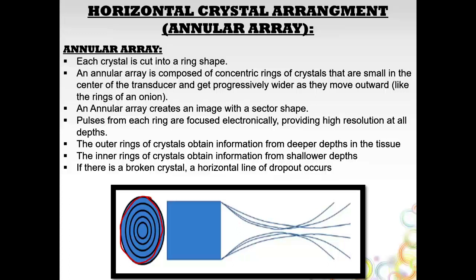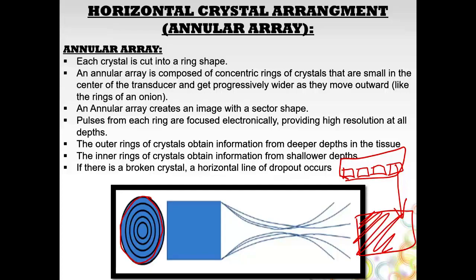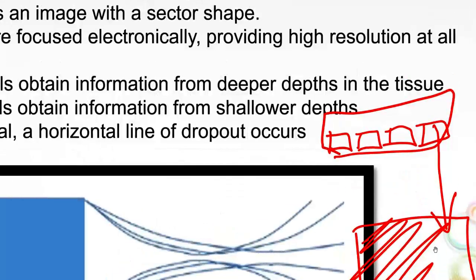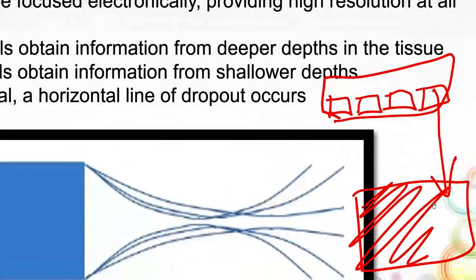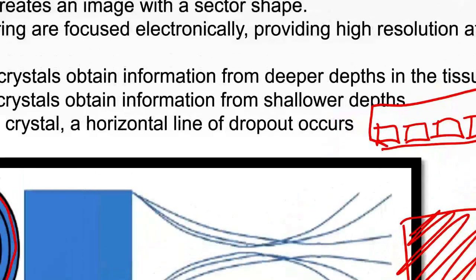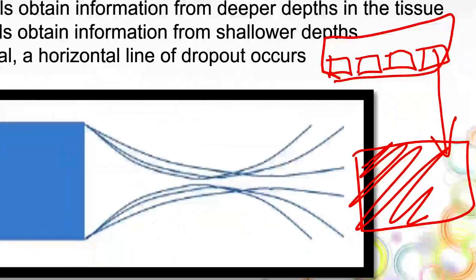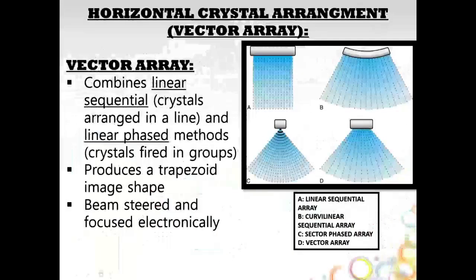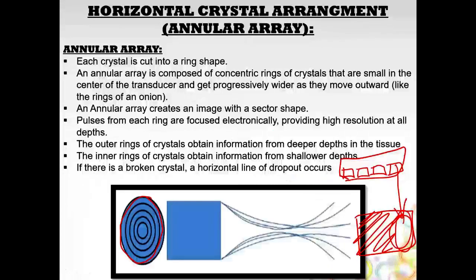And this is something I forgot to talk about in the last slide. So with a transducer, here, you have your row of crystals. If a transducer crystal goes out or is broken, you don't get the pulse or sound wave from that transducer. So on your image, you would have image all in this area, and then where the crystal is broken, this area of the image right in here would have no information in it at all. It would be completely blank, completely black on the screen. And an area of blackness on an ultrasound image means that you've lost the image in that portion of the image.